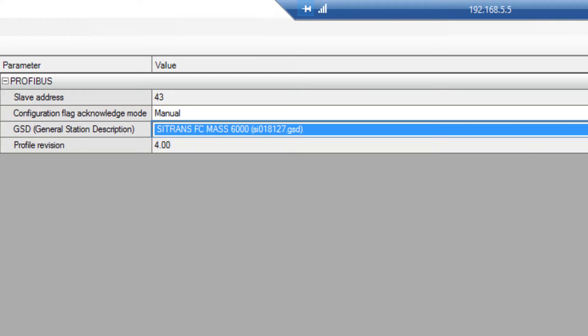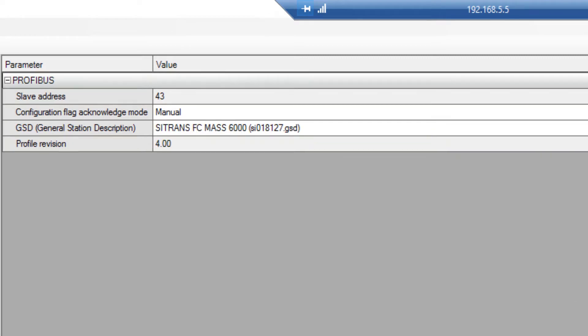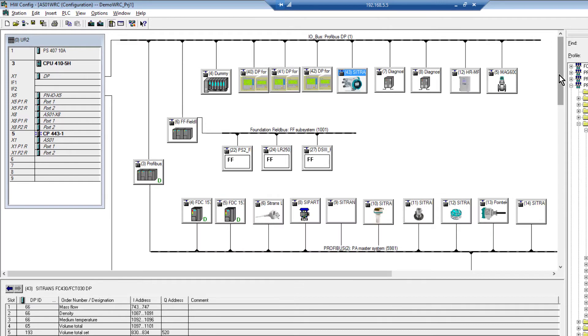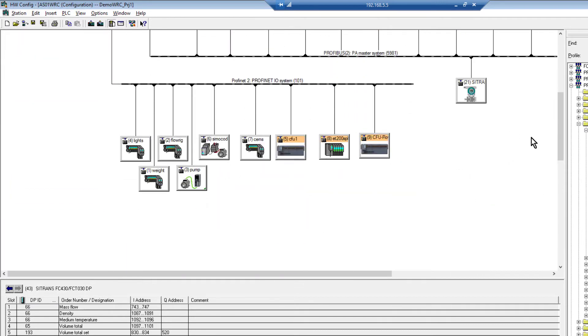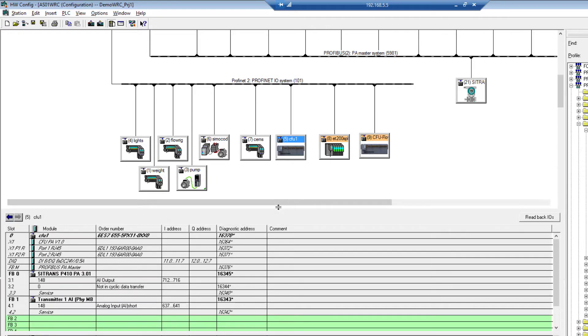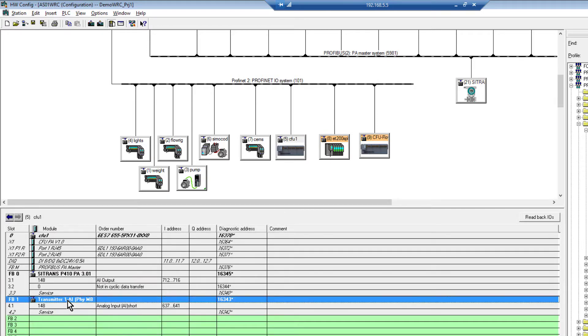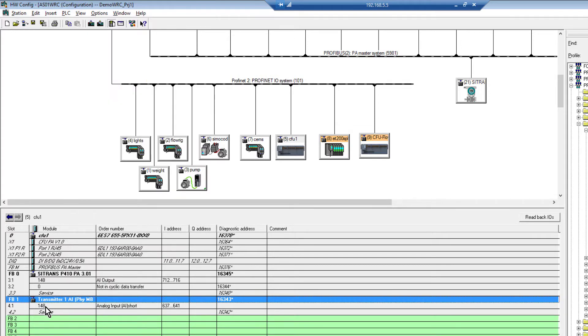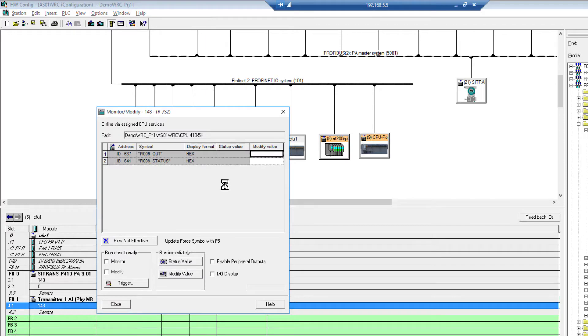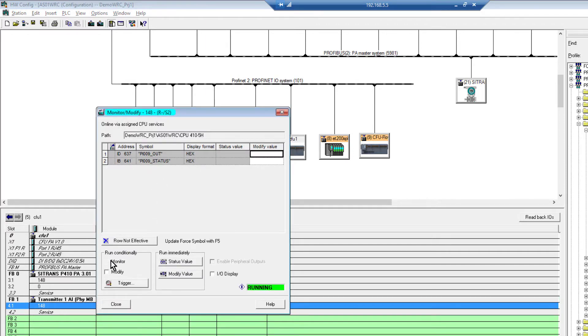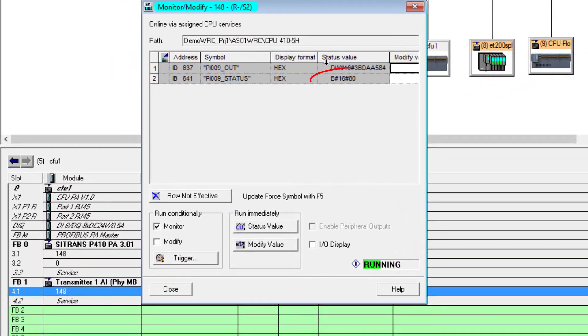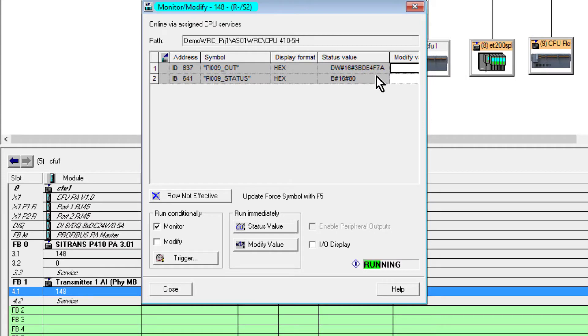Here we have our project and down the bottom I have a Compact Field Unit which currently has a pressure transmitter plugged into it. I'm going to monitor my diagnostics from here. I can see there's my status, it's healthy, and then I have my double word which if you converted that would be a floating point word.